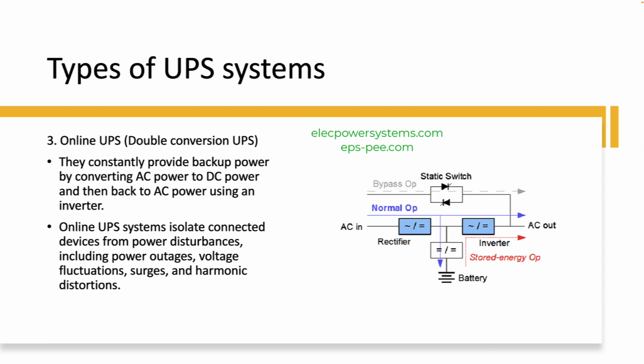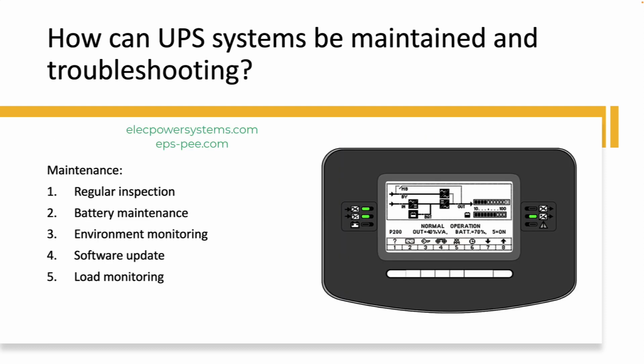Maintaining and troubleshooting UPS systems is important to ensure their proper functioning and reliable operation. Here are some maintenance and troubleshooting steps for UPS systems. Maintenance. Regular inspection. Perform visual inspections of the UPS system, including the battery, connections, and indicators, to check for any signs of damage, corrosion, loose connections, or leaks. Battery maintenance. Monitor battery health regularly, including checking the battery voltage, capacity, and runtime. Follow manufacturer guidelines for battery maintenance, such as performing periodic battery tests, cleaning battery terminals, and replacing batteries as needed.